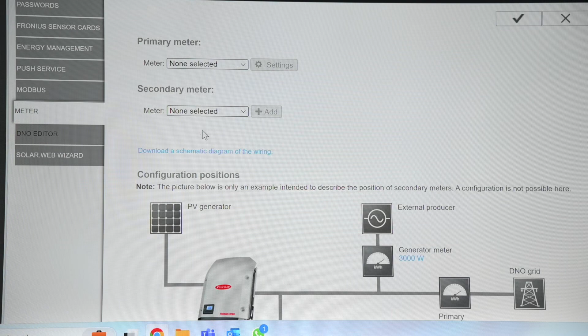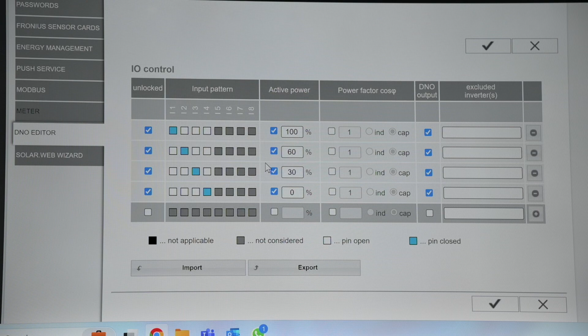Okay, so we'll go to DNO and make sure that our controlling priorities are set as controlled by Modbus at the top. With the I/O control, this is also where you can use a ripple signal coming in from a DSE controller genset, for example. So if the ripple controllers receive that the inverter is running at 30% because the generator is running, we can then enable those settings, but only if need be on the site itself. Again, it's not full genset protection in a sense. You do run the risk of pushing against the generator itself. No limit, because we are controlled via the Victron itself. We just need to make sure that that's selected.